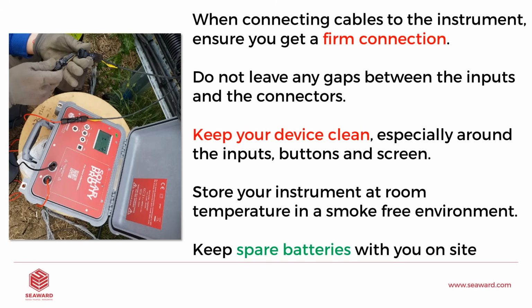Whenever possible, store the instrument at room temperature, okay, in a smoke-free environment. I've had instances where, particularly out in maybe Minnesota where it's very, very cold, the instrument has been left in the van overnight or the truck. And then when we come to test it, there is a fault because it's not actually operating within its operating temperatures. So we just need to be very careful. Similarly, with very hot environments, electronics don't really like very hot environments, right? So we need to keep it within the operational temperature. And I would also advise to keep spare batteries with you at all times.